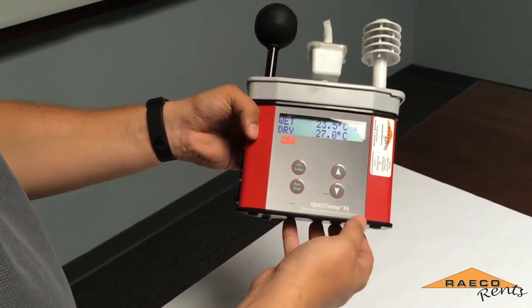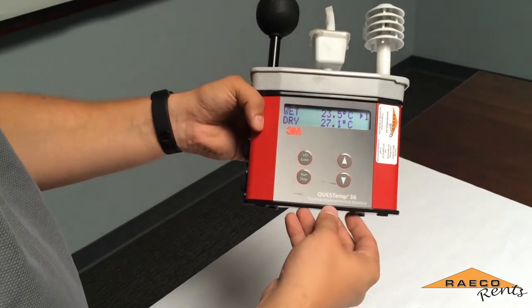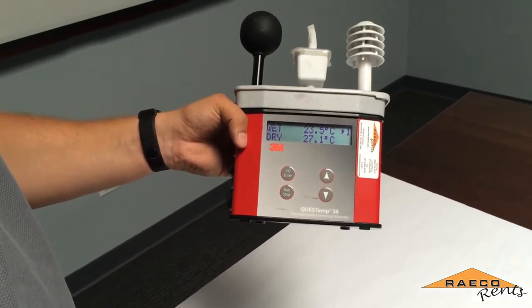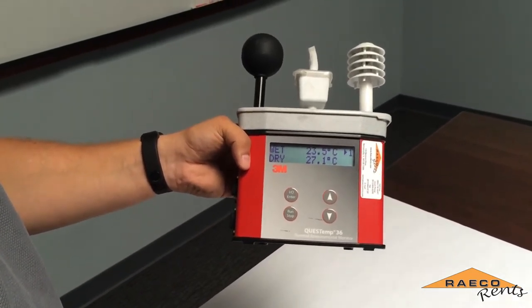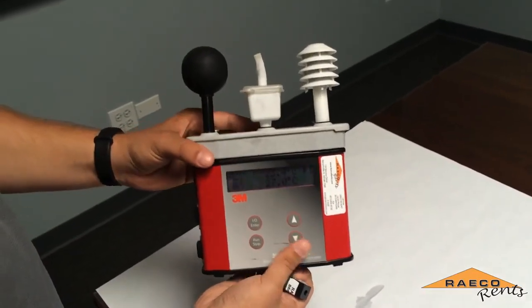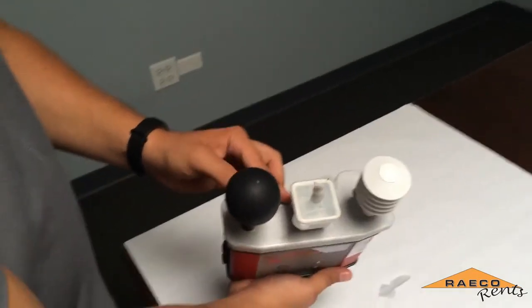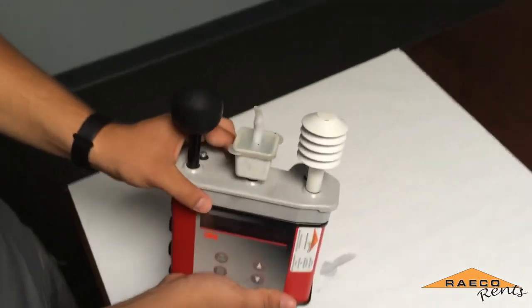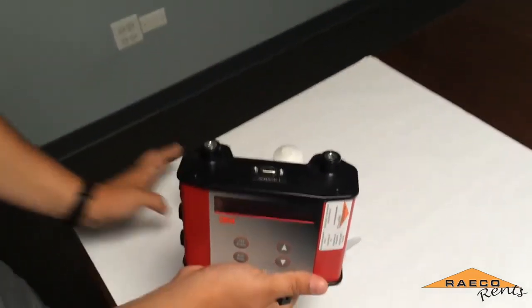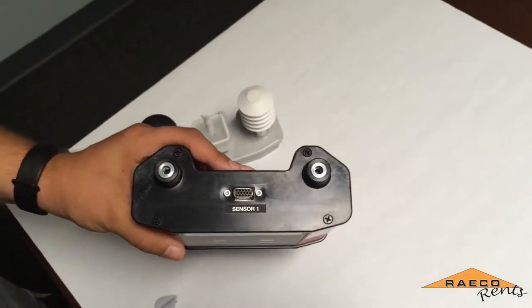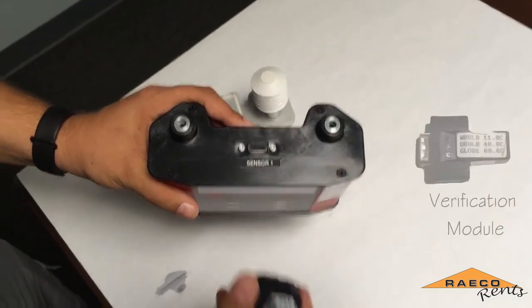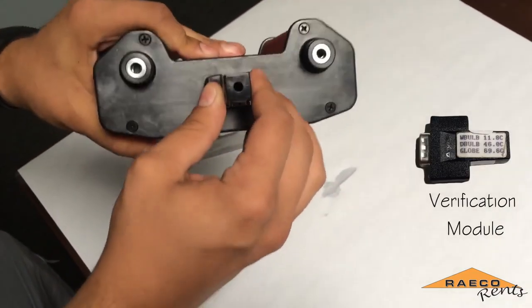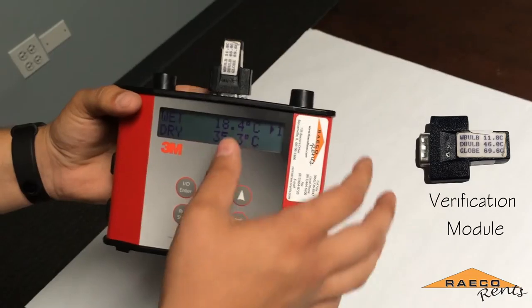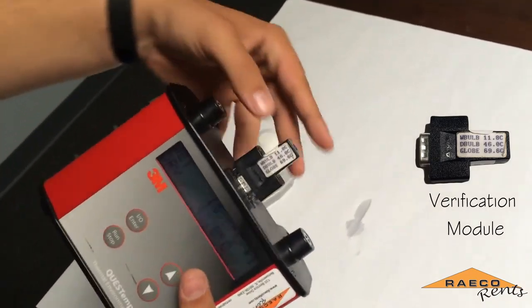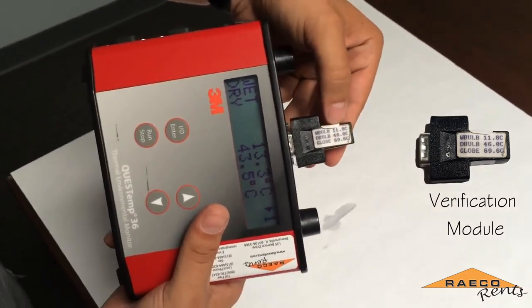I set this in Celsius in order for us to quickly test to see if the instrument is within calibration. In order to do that, we simply undo these screws at the top and we pop off this top sensor bar. Here, that leaves an input for our verification module. Plugging that in will change the readings, and as you can see here, there are values printed for what will be displayed.